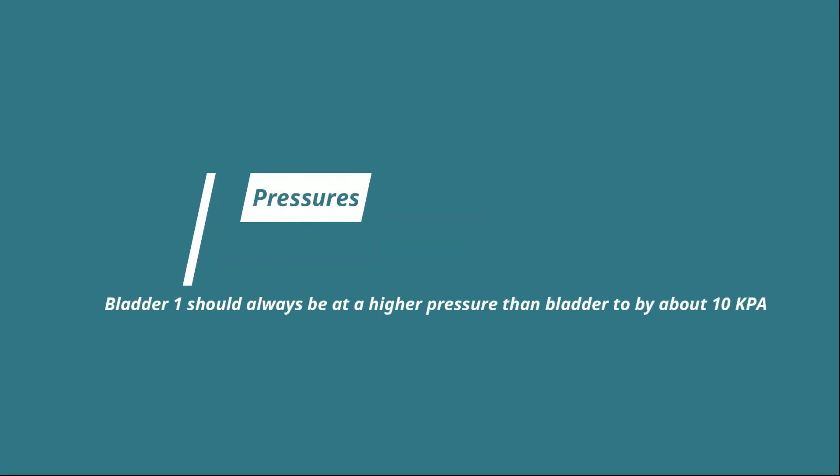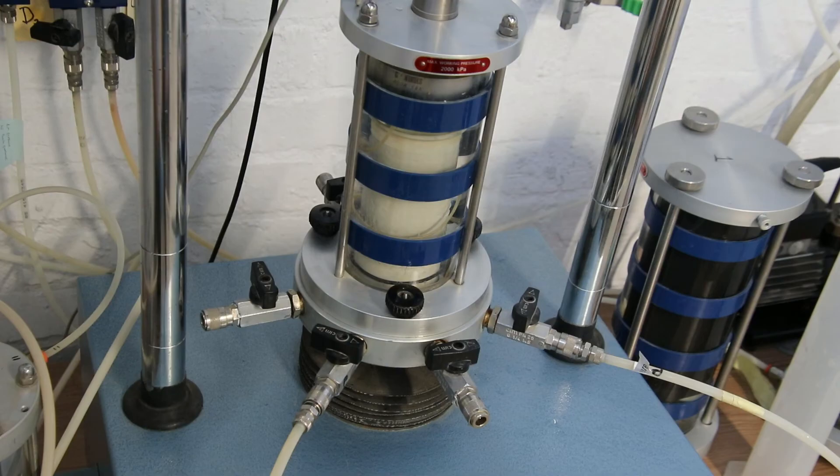Some notes on pressures: bladder 1 should always be at a higher pressure than bladder 2 by about 10 kPa. For example, in a 50 kPa unconsolidated undrained (UU) test, bladder 1 pressure will be at 50 kPa while bladder 2 pressure will be at 40 kPa. For a 35 kPa UU test, bladder 1 will be at 35 kPa while bladder 2 will be at 25 kPa.